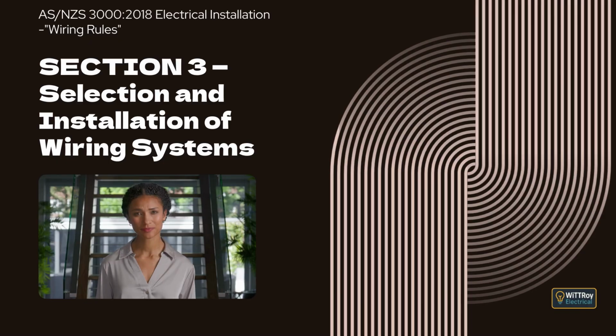Clause 3.3.2.6 Mechanical damage. This clause requires wiring systems to be selected and installed to reduce the risk of mechanical damage. Protection can be provided by the inherent strength of the wiring system, by choosing a suitable location, or by adding local or general mechanical protection, or by a combination of these methods. Clause 3.3.2.7 Vibration. This clause means wiring systems exposed to vibration that could cause damage, including cables, fixings, and connections, must be suitable for those conditions.